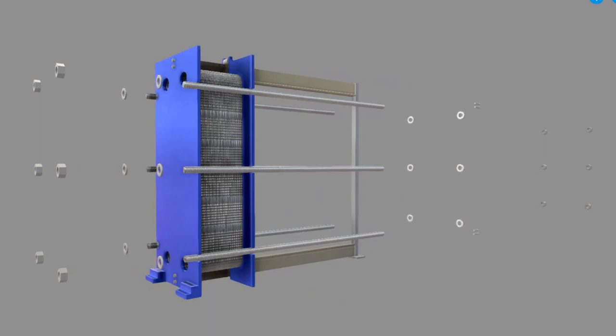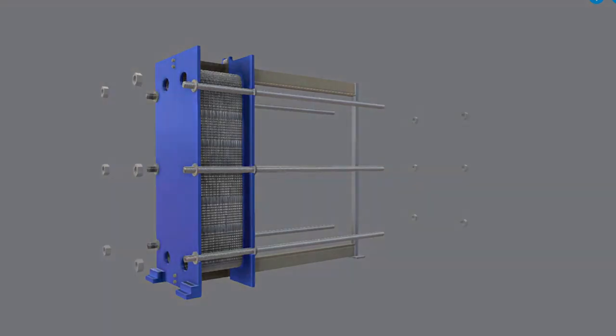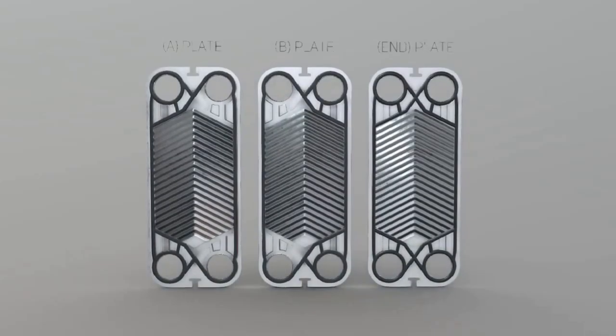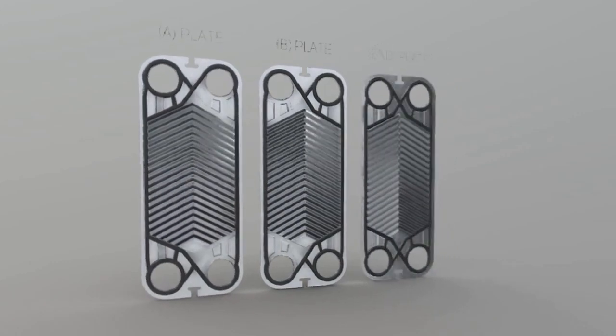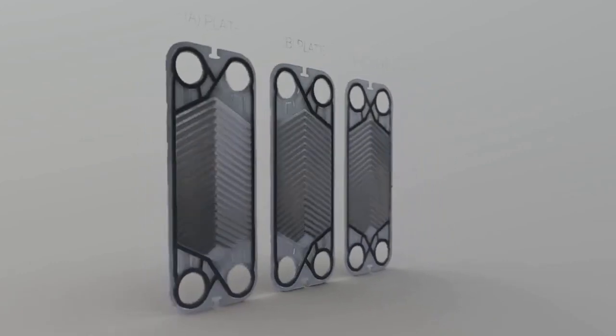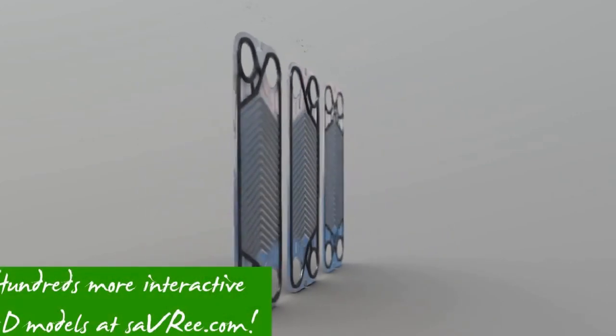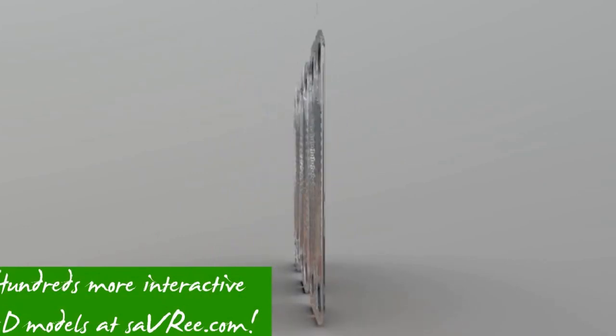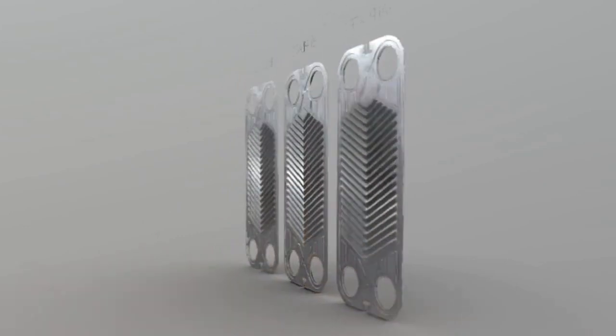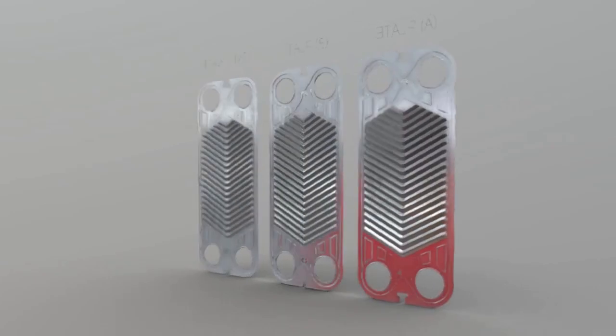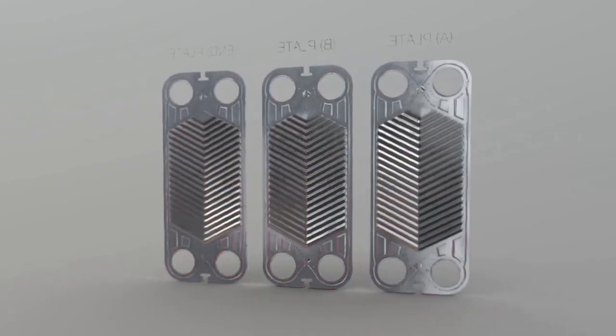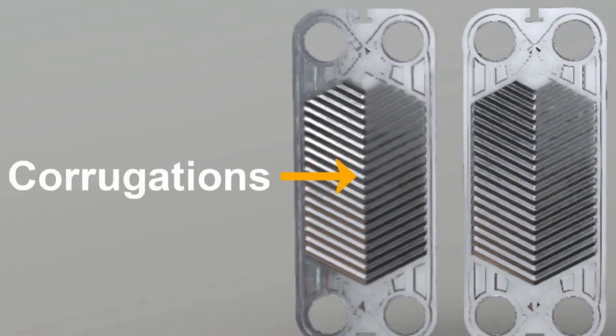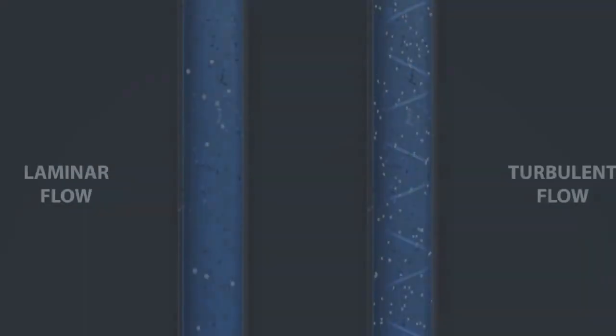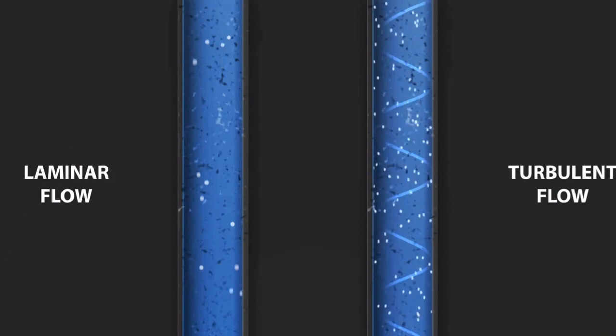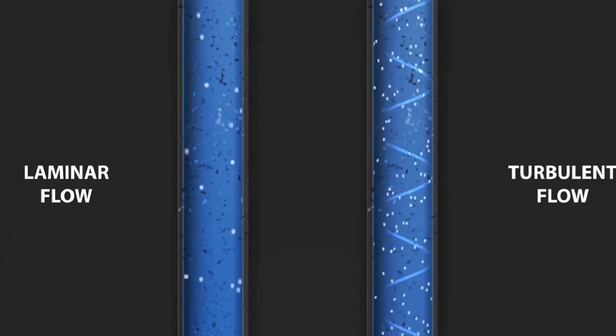The gap between the plates is also known as clearance. Plates are thin and have a large contact surface area, which gives each plate a high heat transfer rate. Plates are manufactured from a material with high thermal conductivity, which further increases the heat transfer rate. Corrugations on the plate surfaces prevent laminar flow and promote turbulent flow, which increases the heat transfer rate whilst also reducing the likelihood of deposits accumulating upon the plate surfaces.